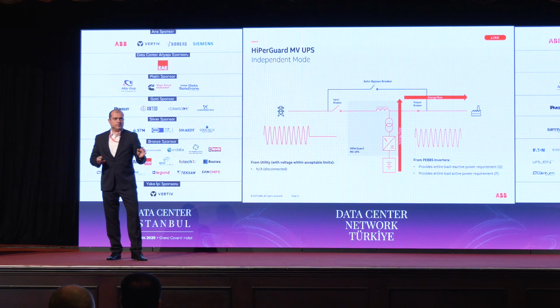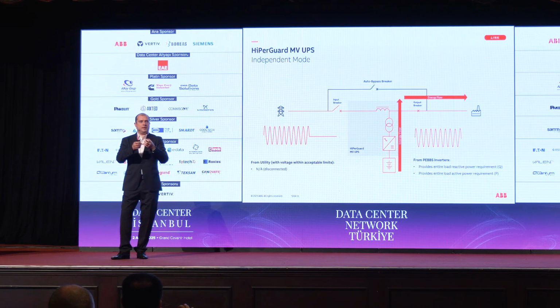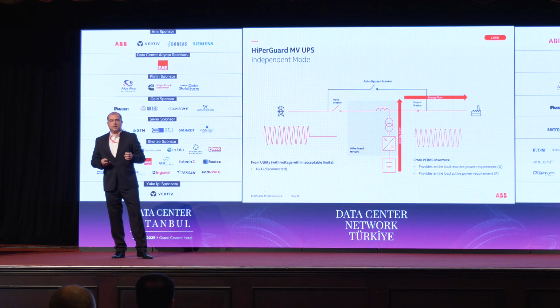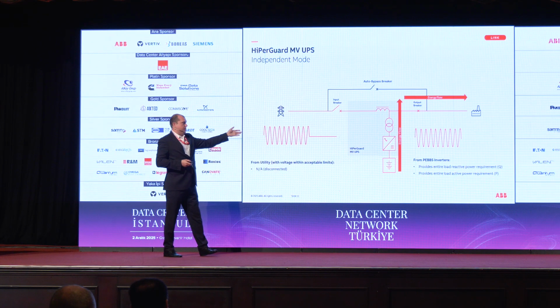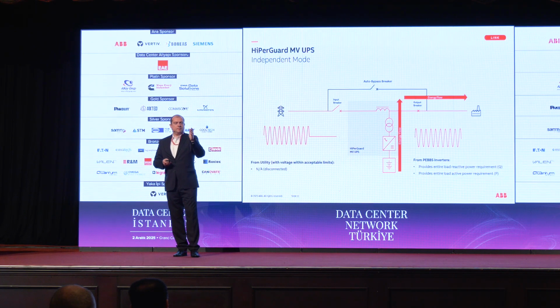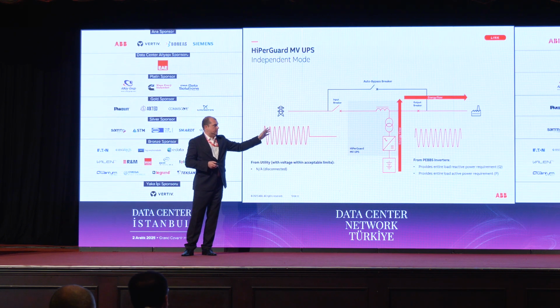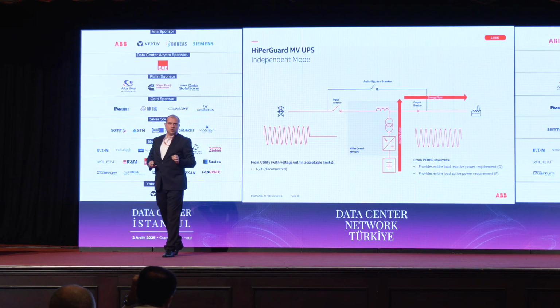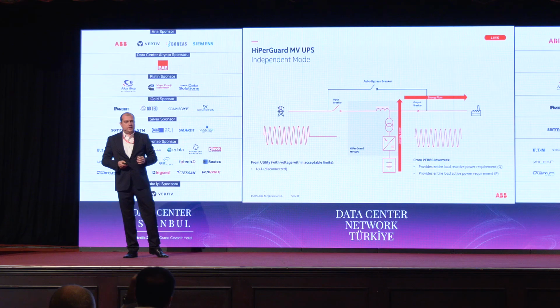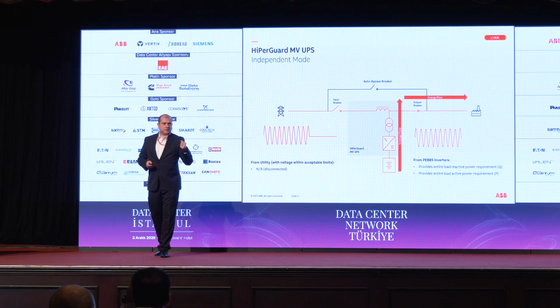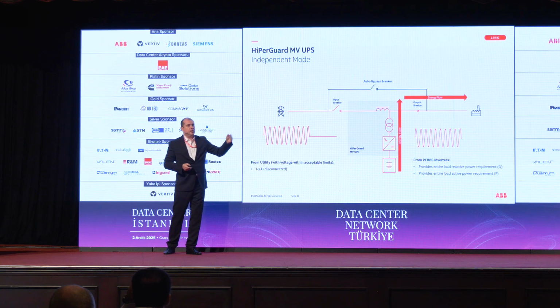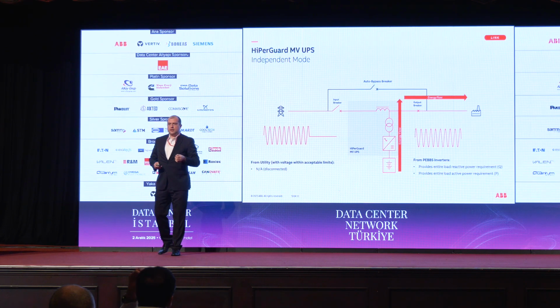Load is protected. So it is not only the functionality of the UPS, but the automation of the UPS working in harmony with the switchgear and with the batteries. This is the principle of the medium voltage. Of course, in this case, the UPS memorizes the exact tempo, pace, phase shift, and all of the other parameters needed to continue the perfect sine wave back to the load. Once the grid is okay, and we have the time to trust it, we reclose this circuit breaker and continue to work on the grid as it should be.